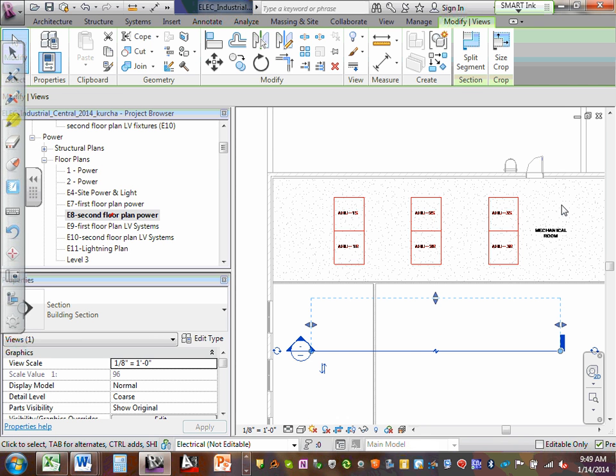Duct detectors are not required to evacuate the building. They're simply there to shut the unit down. Why do we shut the unit down? The code wants us to do that so that we avoid spreading smoke in a building through the air handling system.